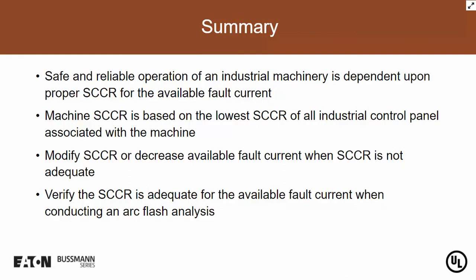And then we've got number 3, modify the SCCR or decrease the available fault current when SCCR is not adequate. If we find out that we do not have adequate SCCR, how do we make it adequate? We either drop the fault current with transformers or conductors, or increase the SCCR by modifying the panel or using current limiting devices. I usually say we're increasing the SCCR of the panel, not necessarily reducing the fault current, but it depends on how you look at it, because you're kind of doing both at the same time.